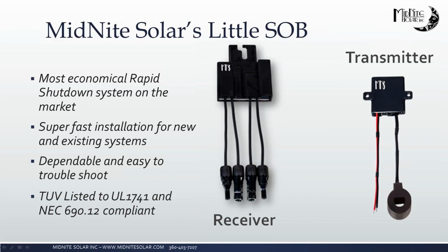The way that this works is you plug the receiver module into the MC4 connectors on your panels, either on the first module in the string or onto every module of the string, depending on which code you are trying to meet. It does meet the new 2017 code that goes into effect January 1st of 2019 for the modular shutdown. What the transmitter does is it sits on the PV positive line and it induces a PLC signal into that line, which gives a keep-alive signal to the receiver. And as long as it is receiving that, it does allow power to come from the panels. As soon as it does not see that signal anymore within 5 seconds, it will shut down that system.